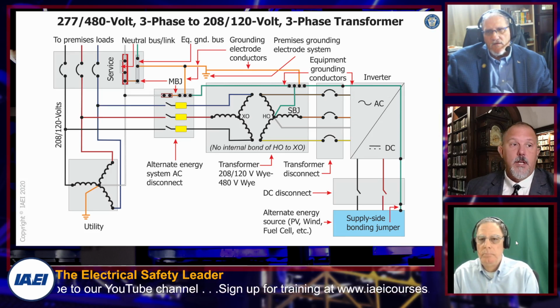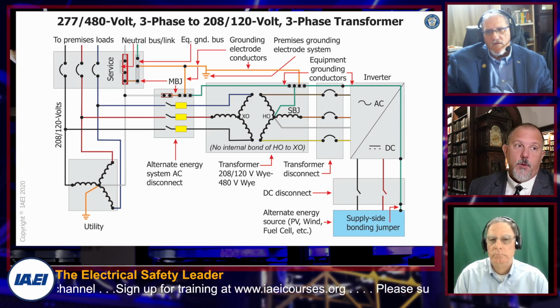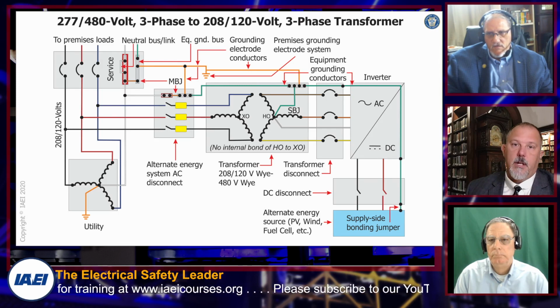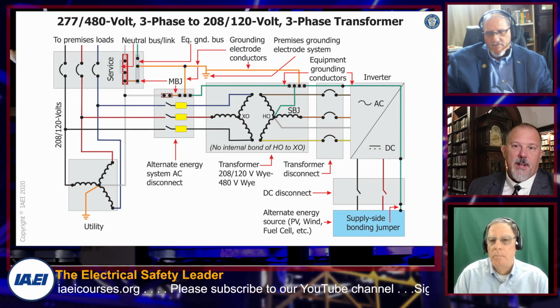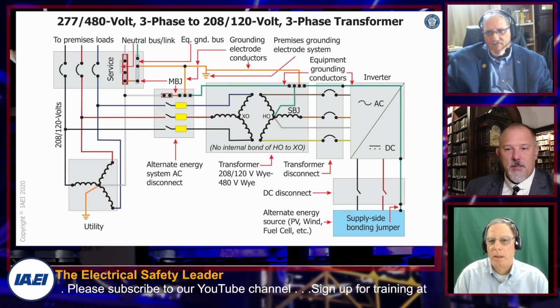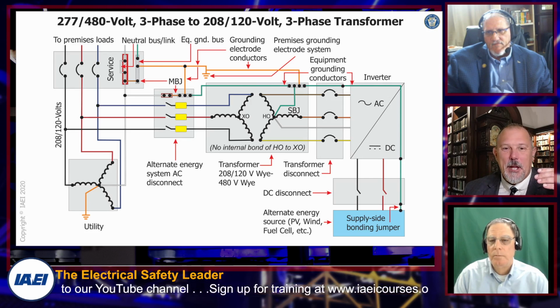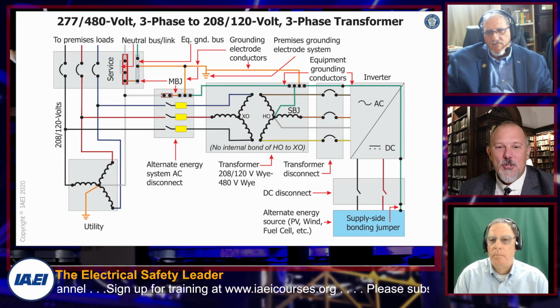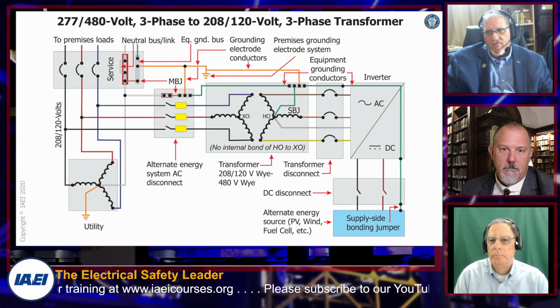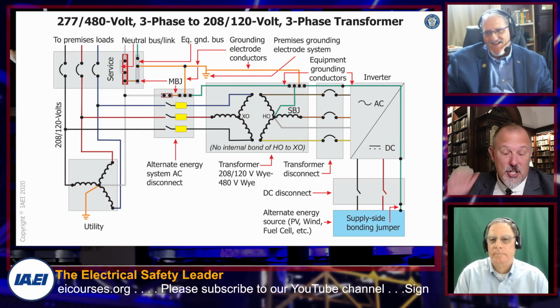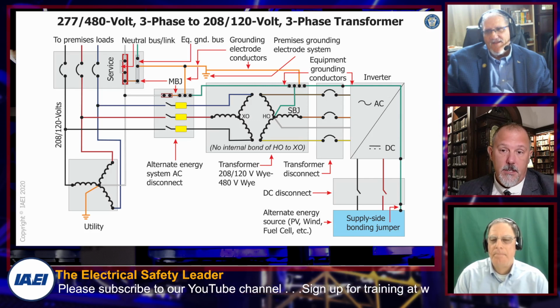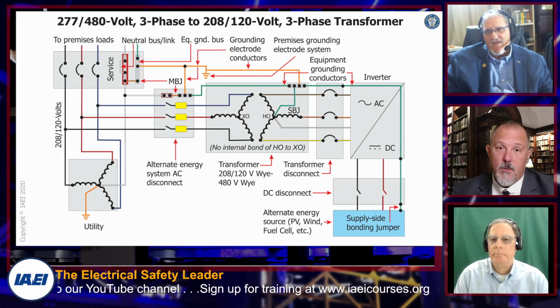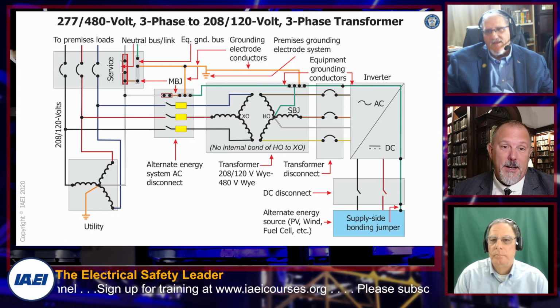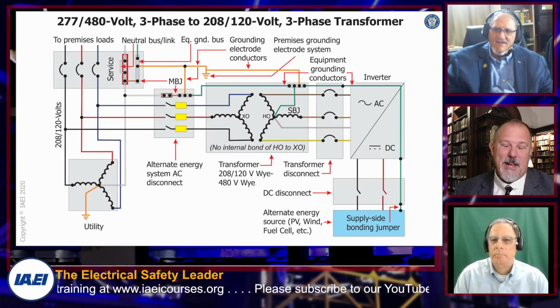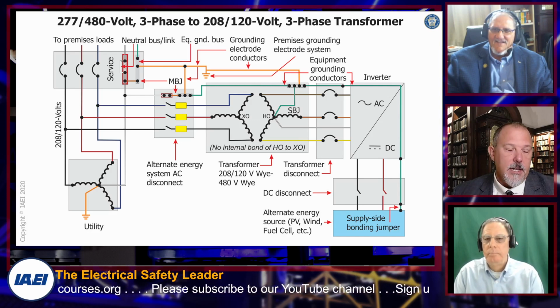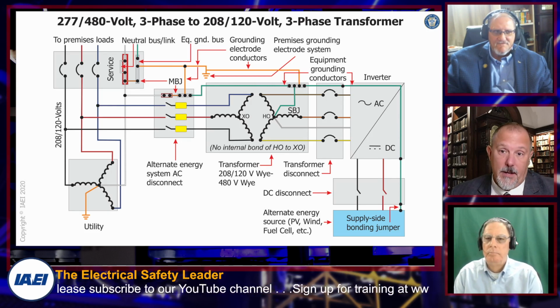In a PV type of system, I know from personal experience that you may have a very beautiful PV installation where it looks like it should be on the cover of a magazine. But I've been with an electrical inspector on a big flat roof, and as we got closer to the installation, he stopped, turned around, and said, put both of your hands in your pocket and don't touch anything. Then he started to show me all of the bonding issues in that installation where things were not bonded. His comment was, I don't know if there's a potential here, but there is a potential here, and we don't want to find out anything else about this installation by touching anything, because bonding is critical in those applications. And in some cases, it's not done correctly at all.